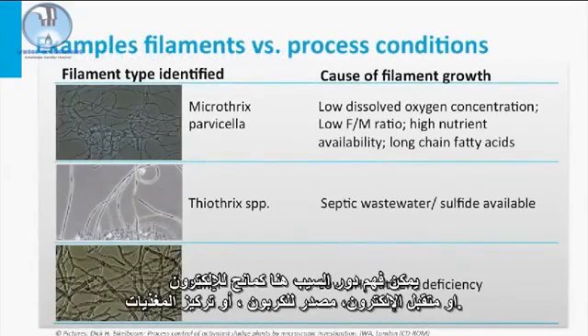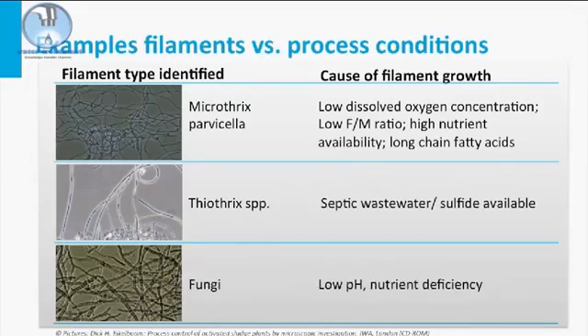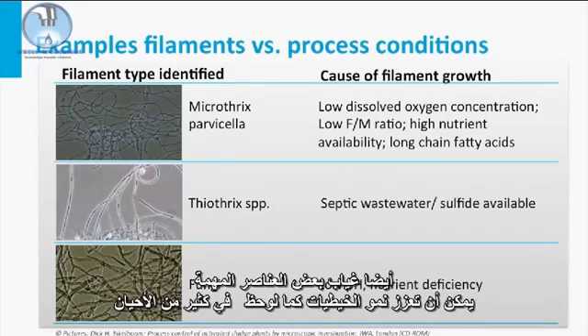Indeed, as substrate concentrations in the bulk liquid are low, the filaments will proliferate. Substrate can be understood here as electron donor, electron acceptor, C source, or nutrient concentration. Also, the absence of certain trace elements can enhance filamentous growth, as more often observed in industrial wastewaters than in sewage treatment.